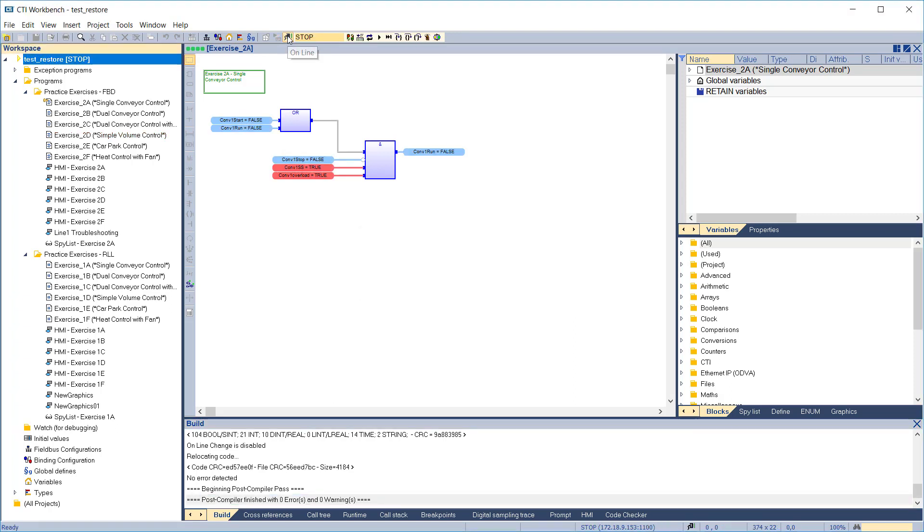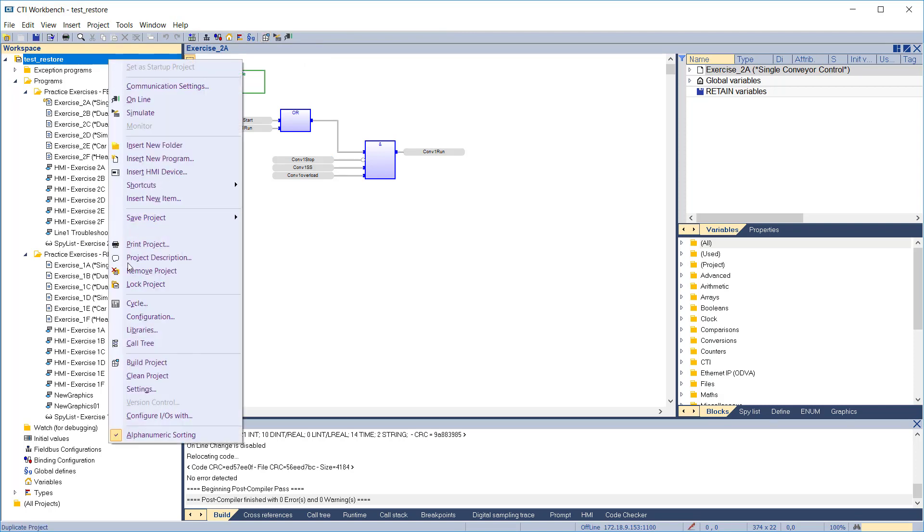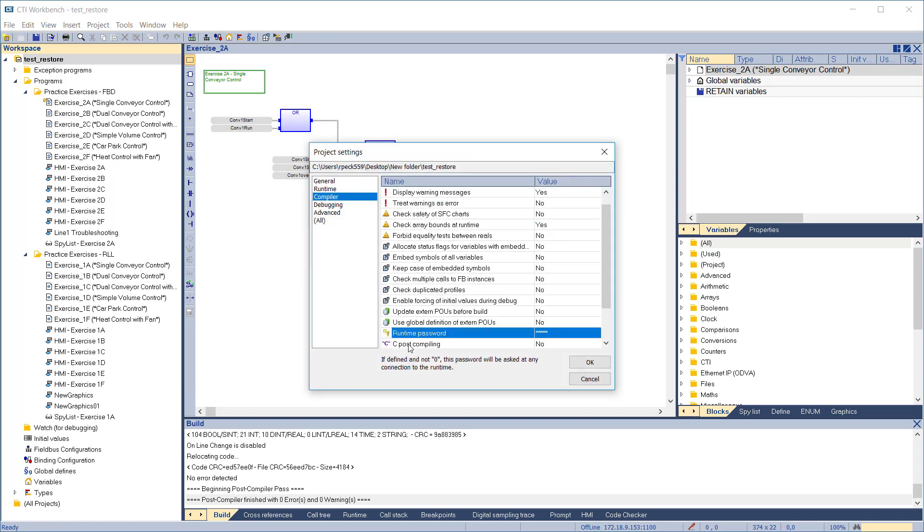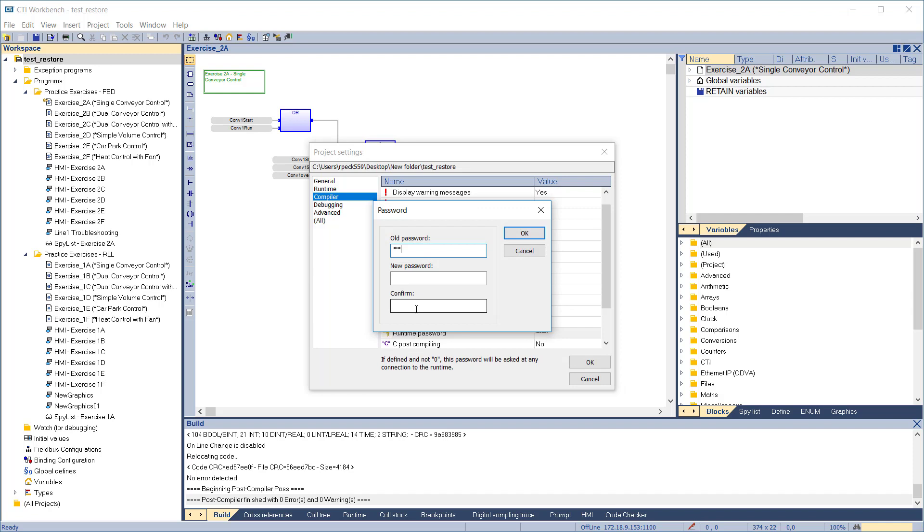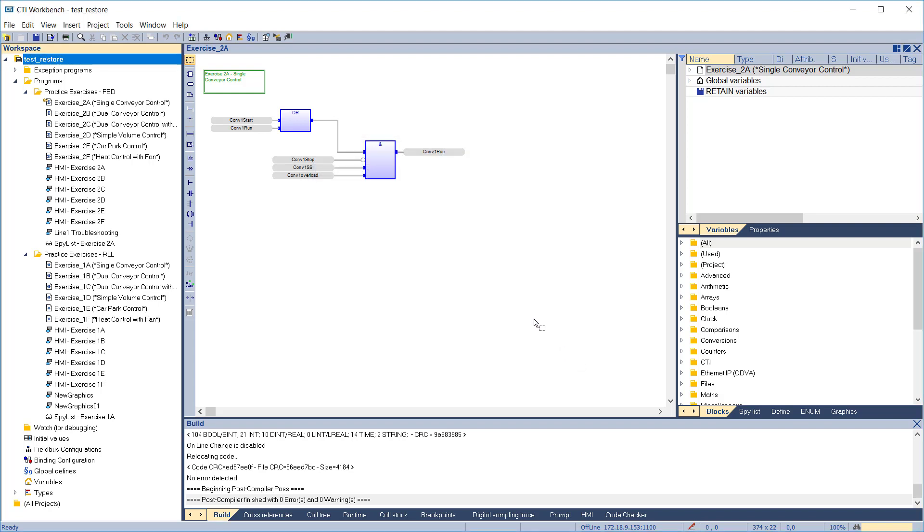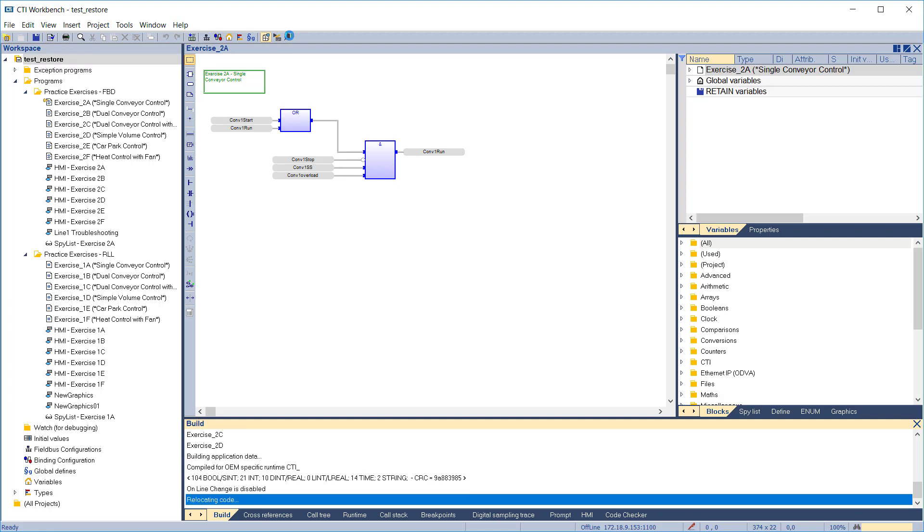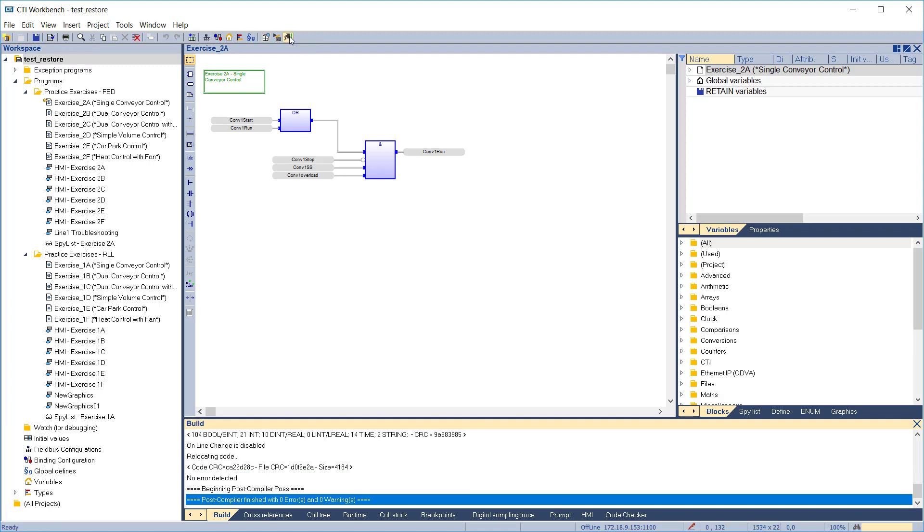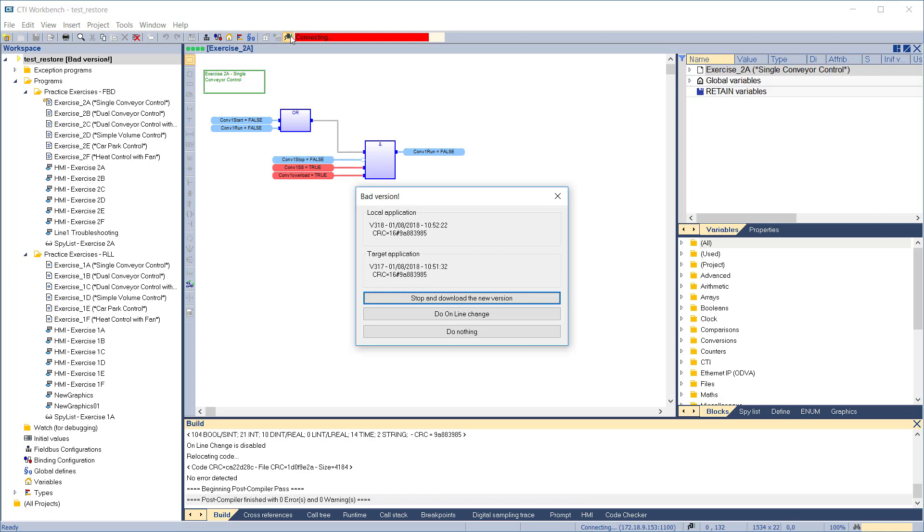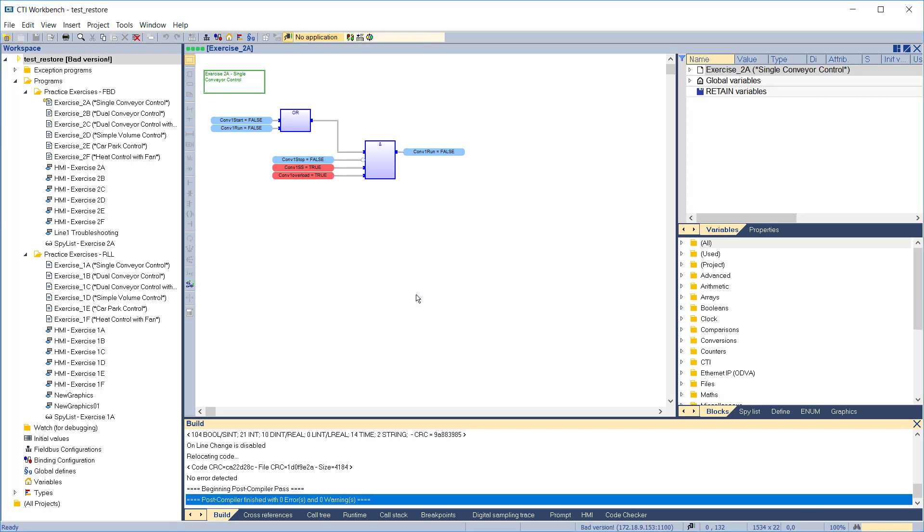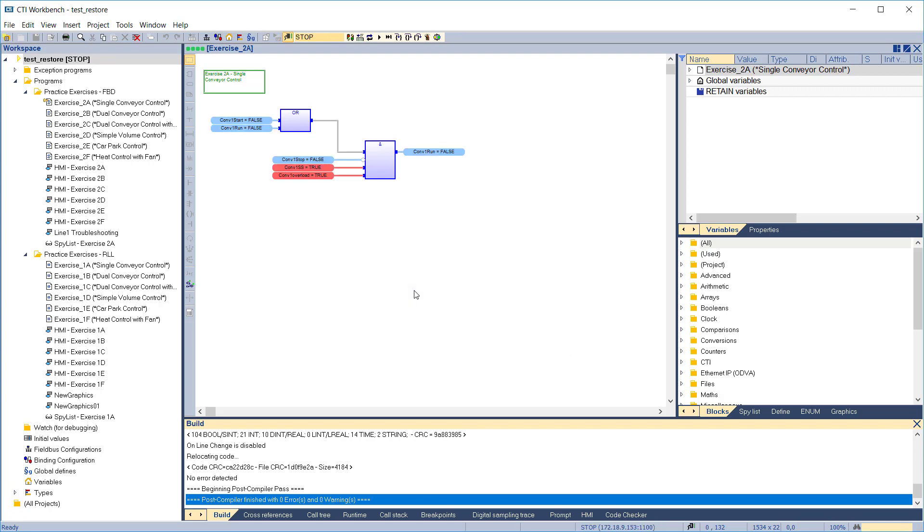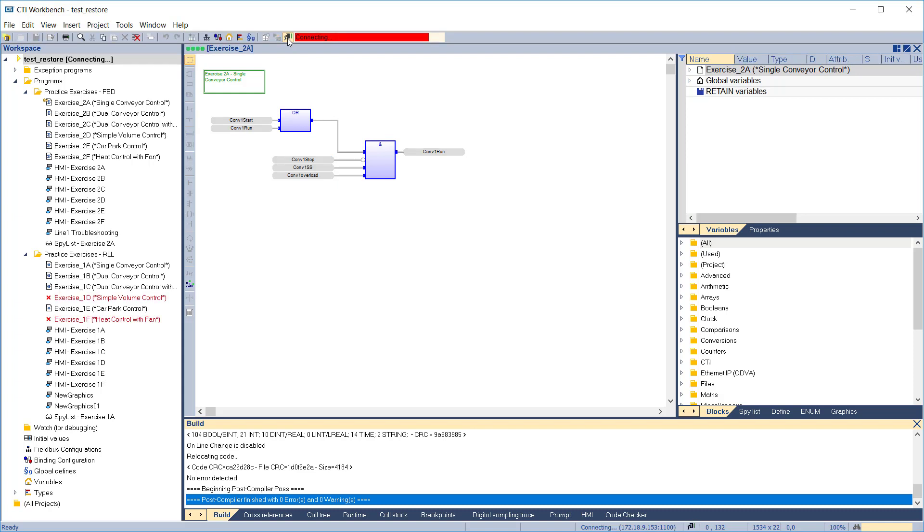To clear the password, we'll disconnect, then edit the project settings again and put in an empty password. Recompile. Connect. We must provide the old password because it's still active in the target. Now download the new version without a password. Then disconnect and reconnect to check. This time, we're not asked for a password.